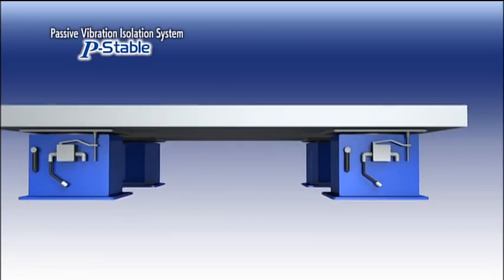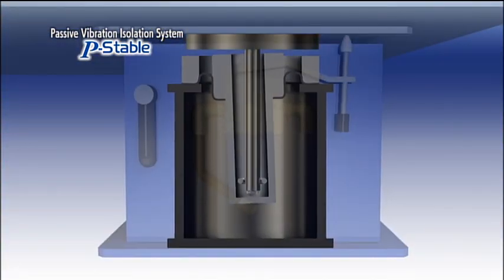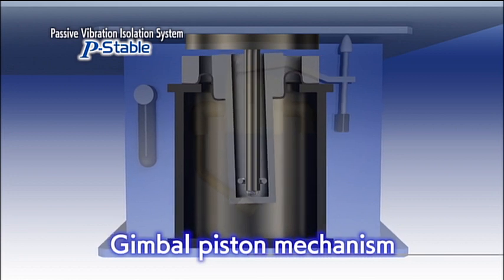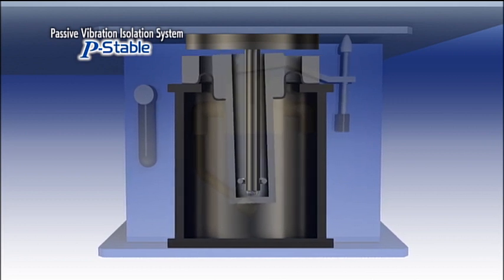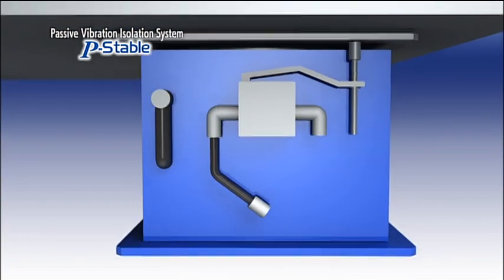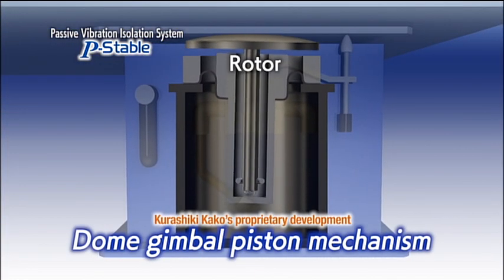Kurashiki Kako's passive vibration isolation system P-Stable is noted for its gimbal piston mechanism air spring. A gimbal piston mechanism is an air spring with a gimbal mechanism assembled inside. The gimbal piston is a very compact mechanism with excellent vibration isolation in the horizontal direction and has a reputation for being the best mechanism for a passive vibration isolator. However, at Kurashiki Kako, we have added a rotor to this mechanism, creating the dome gimbal piston with even higher horizontal vibration isolation.